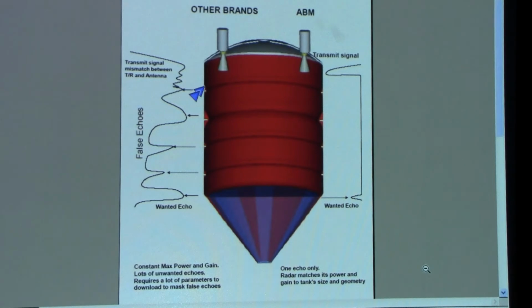When you look at the right side, you can see the ABM radar, which automatically adjusts its transmit pulse, receiver gain, and transmit pulse length. As a result, we receive only one echo from the liquid or solid material, with the other false echoes pushed under the noise level. This offers a very reliable level measurement system.